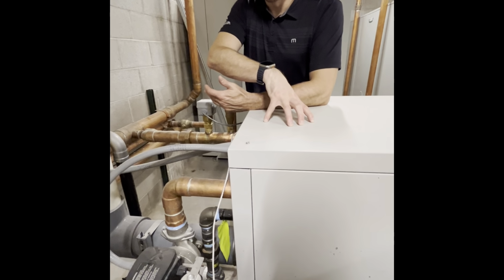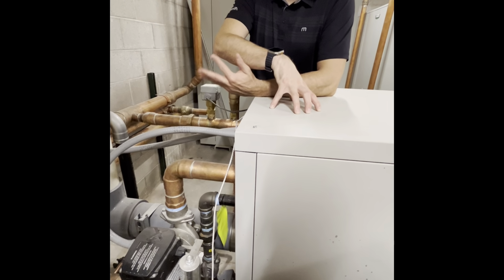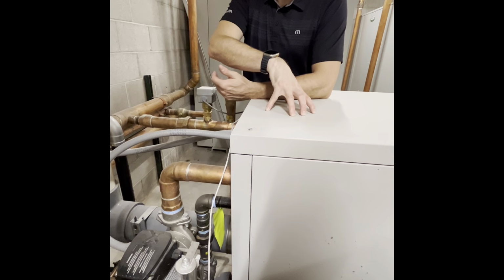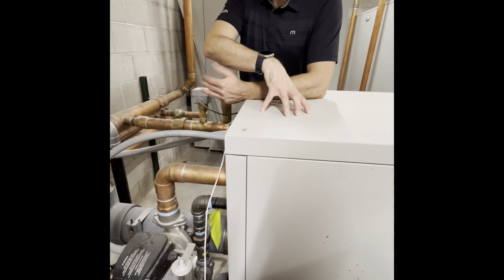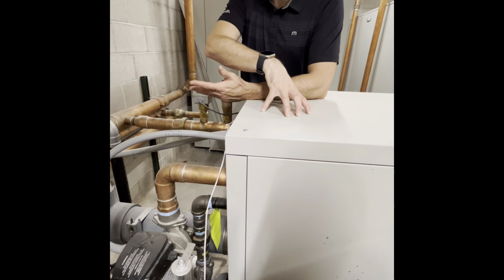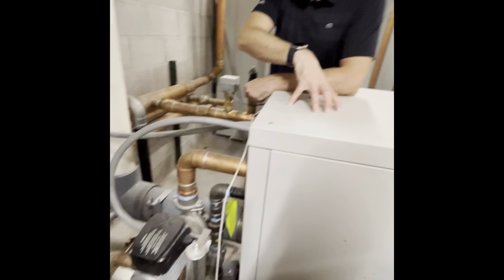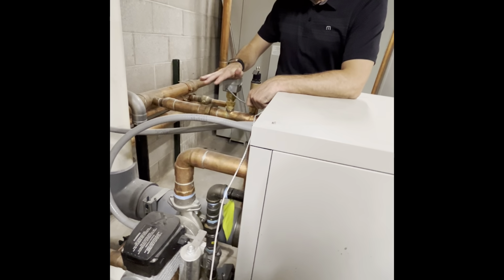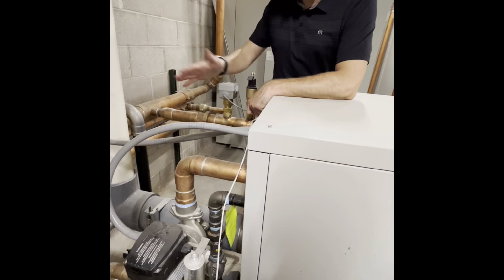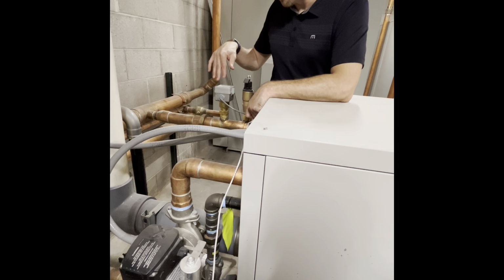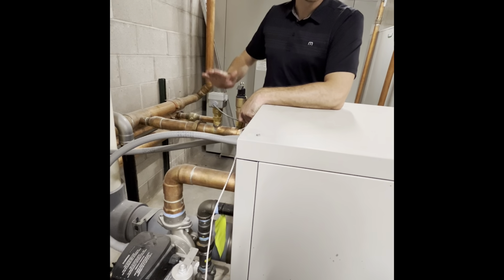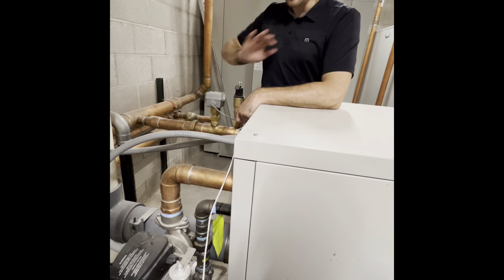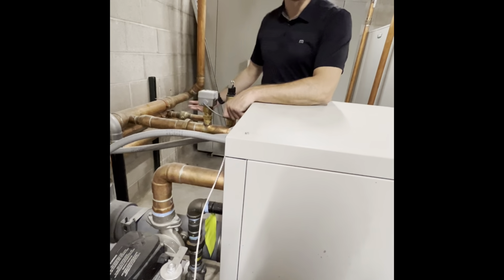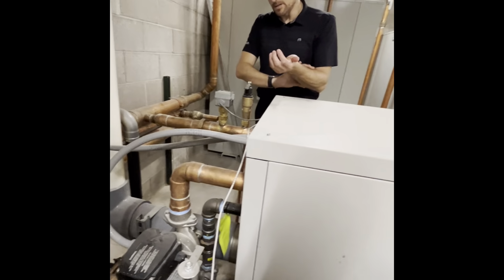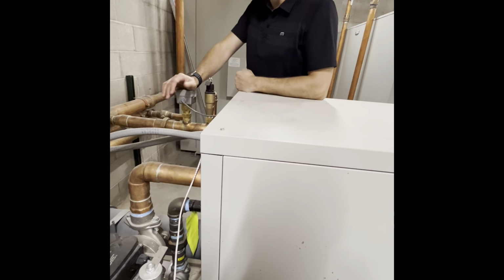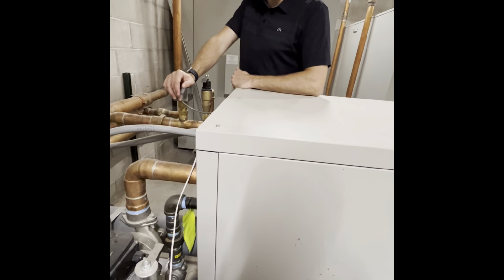If that begins to fail, then you'll see lockouts. So something to keep an eye on if there's any power failures or anything of that nature. That's typically where I tend to look first, is to make sure that that is something that's maintained. Right back up here on the piping, kind of tracking back, you're going to have what's called the flow switch, meaning this is just going to make sure the water's flowing out of the heater and downstream properly, so it's not coming back upstream. So just making sure, the old adage in plumbing, that stuff flows downhill.